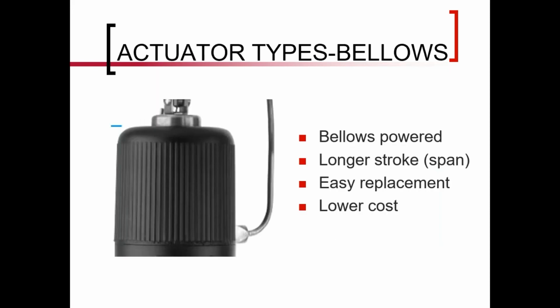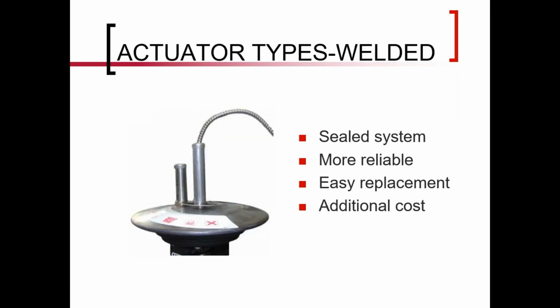So two actuator types are the most prevalent. One is bellows we talked about before, and bellows, it can be a stem seal type of product. In this case, it's the actuator, and the bellows will have a fill of some type that, again, condenses, expands, and that's what powers it. These usually have a longer stroke, and the bellows can fatigue over time. They are easily replaceable usually, and then the bellows type is usually a lower cost versus a welded sealed system.